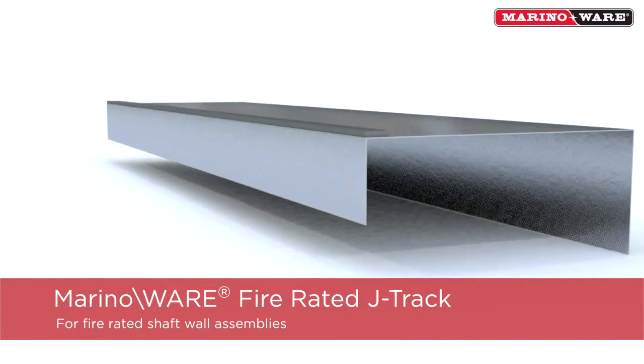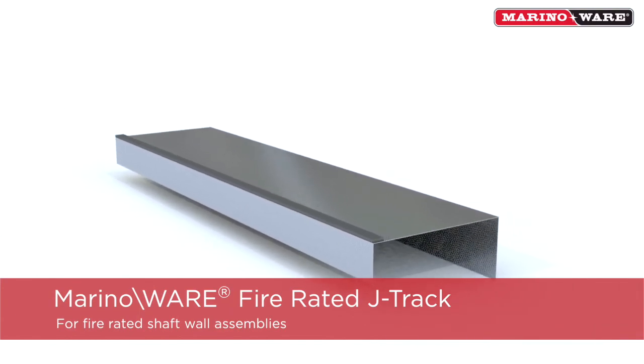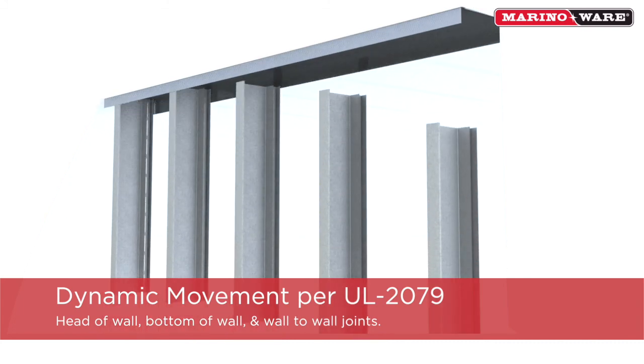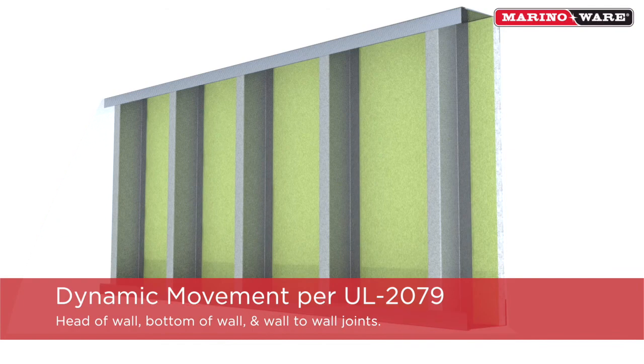Marino\WARE Fire Rated J-Track is a composite steel intumescent J-Track used for shaft wall assemblies that require fire rated dynamic movement, according to UL 2079, at the head of the wall, bottom of the wall, and vertical wall-to-wall joints.